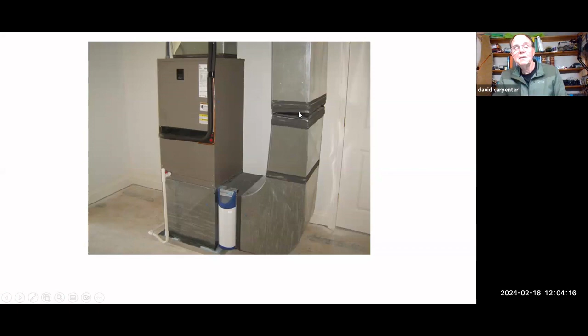They had a transition point in this system. We saw this young man that got electrocuted. They didn't have it in any of the transition points. Here's one newly installed, nothing around the transition points. This is not uncommon. They'll actually put duct tape, as you can see around here. This is poor workmanship, that's all you can say. So if you see it, just write the standard and tell them they've got to meet it. It's just that simple. Everybody's on the same page that way.